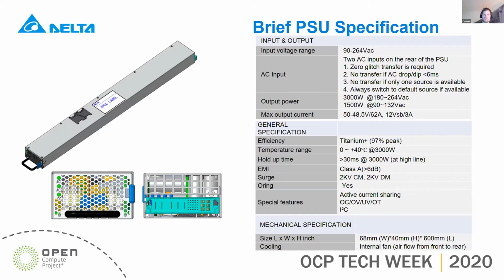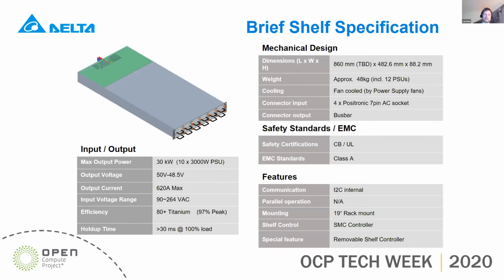The specification of the power shelf on the next slide shows we can plug 12 of these power supplies into the shelf, installing in total 30 kW of power into the shelf as required by the spec. The efficiency here is 97% peak efficiency, also due to the ATS functionality.